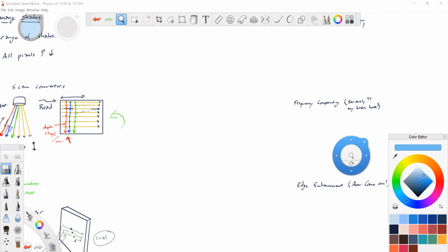Now let's do write magnification. As you're taking the picture, it is magnified. Damn it, I just said that backwards. With read magnification, you took the picture, now you're zooming in, magnifying a small portion of that picture. You're making that region of interest larger, and the spatial resolution technically does not change. Write magnification, you are magnifying before taking the actual picture, before storing the image.